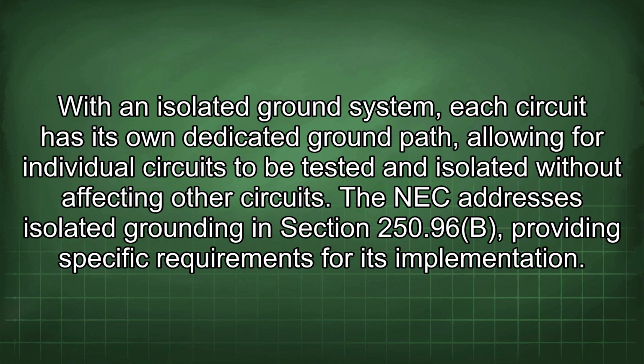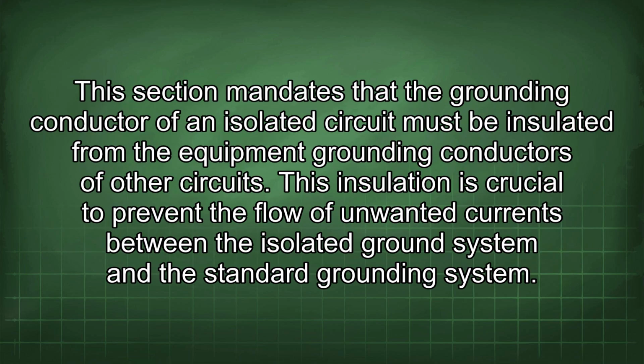The NEC addresses isolated grounding in section 250.96(B), providing specific requirements for its implementation. This section mandates that the grounding conductor of an isolated circuit must be insulated from the equipment grounding conductors of other circuits.